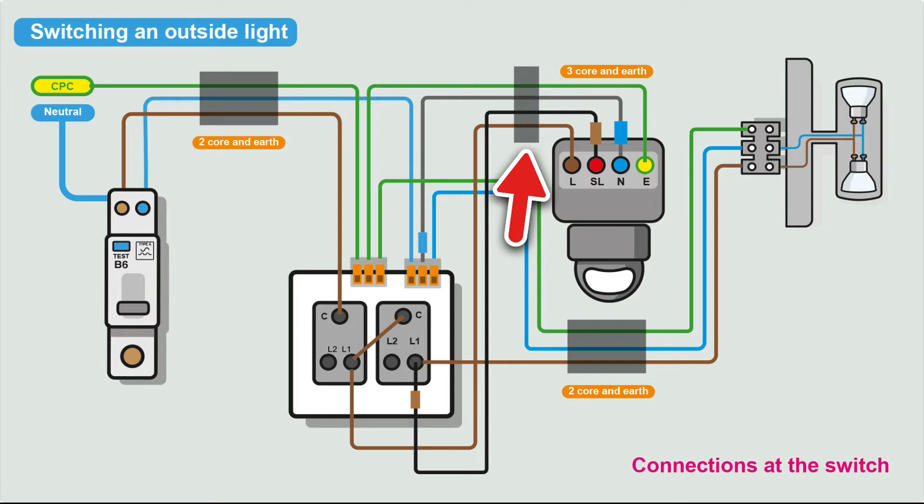In three-core and earth, you've got the brown, black, and grey. The brown would be a permanent live. The black would be a switch live, which you would add some sleeving to each end - some brown sleeving to indicate it's a live conductor, a switch live conductor. And the grey cable would be the neutral, which we would sleeve with blue to indicate that it is the neutral.